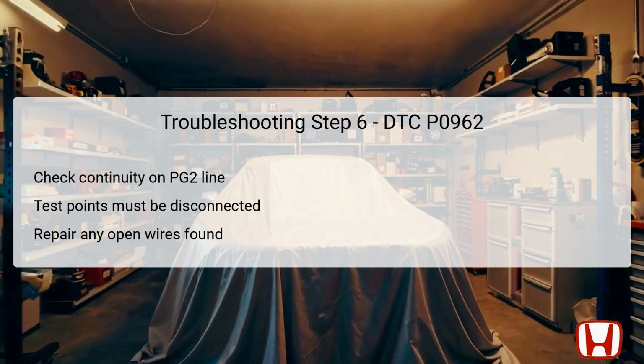interference during testing. If continuity is confirmed, it indicates that the PG2 wire is functioning properly, allowing for a transition to Step 7. Conversely, if continuity is absent, this suggests an open circuit that requires careful inspection and repair between the solenoid and ground reference. Addressing any identified open circuits is crucial for restoring proper solenoid function.